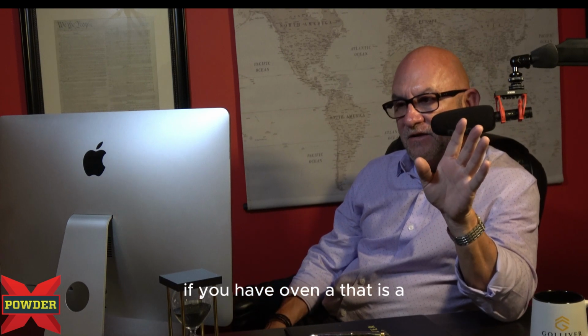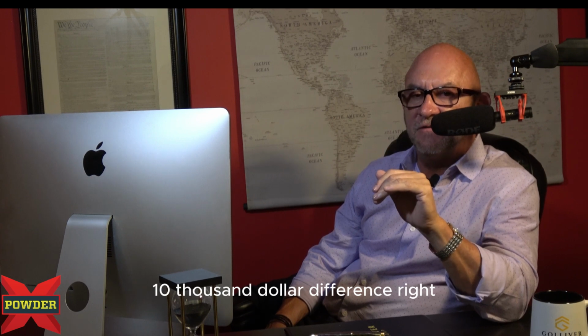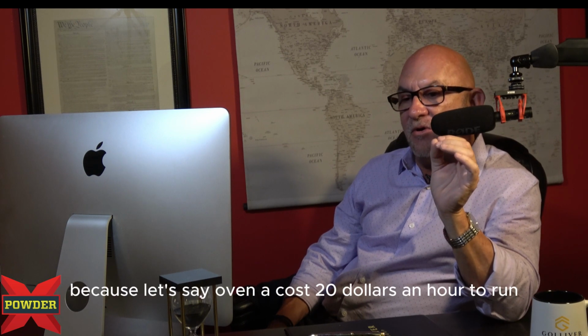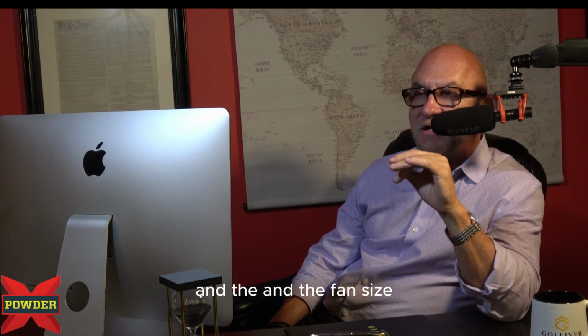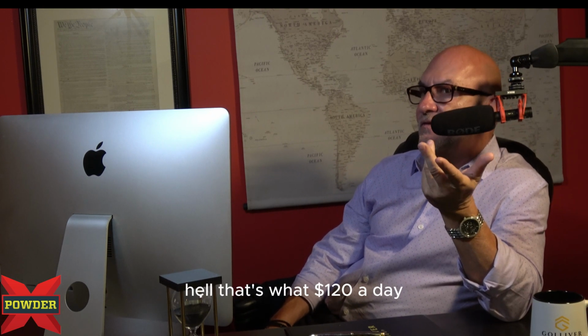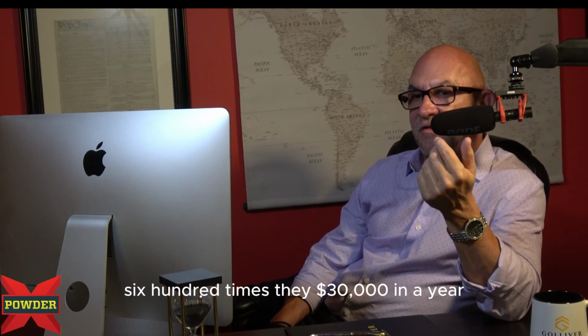If you have oven A that is a $30,000 oven and oven B is a $40,000 oven, a $10,000 difference, right? Jump on the one that's less expensive, correct? Not necessarily, because let's say oven A costs $20 an hour to run and oven B costs $5 an hour to run, all because of the burner and the turn down ratio and the fan size and all the engineering that goes into it. At $15 an hour difference at 8 hours a day, that's $120 a day, that's $600 a week, 600 times 50, $30,000 in a year.